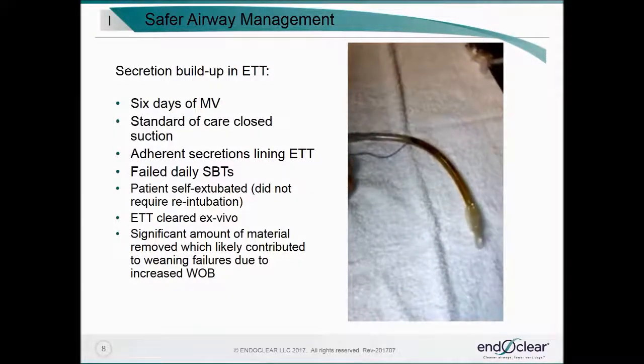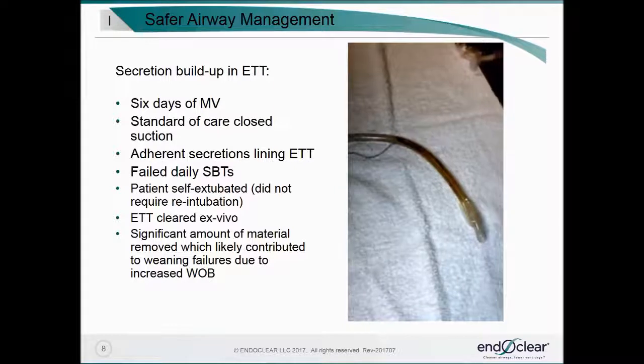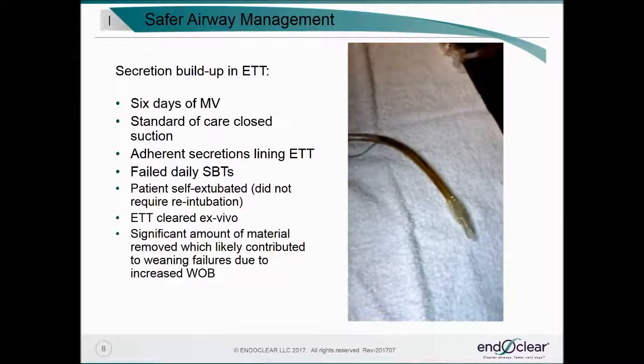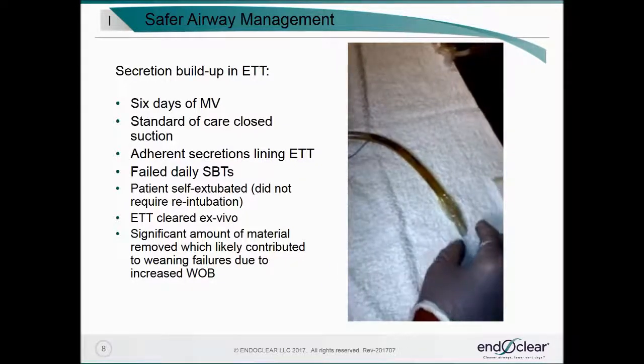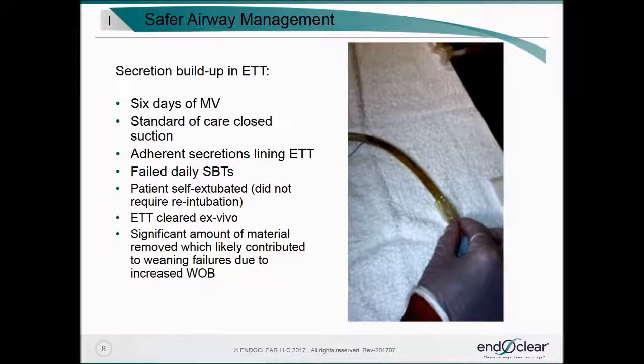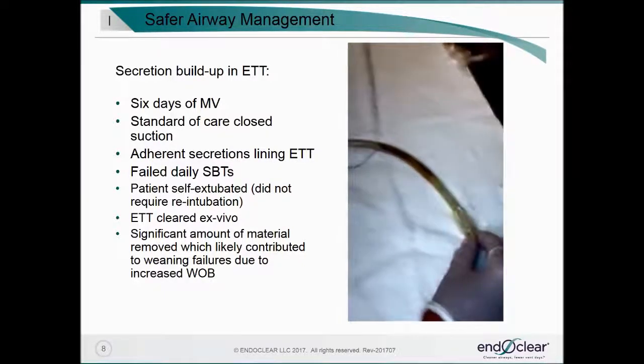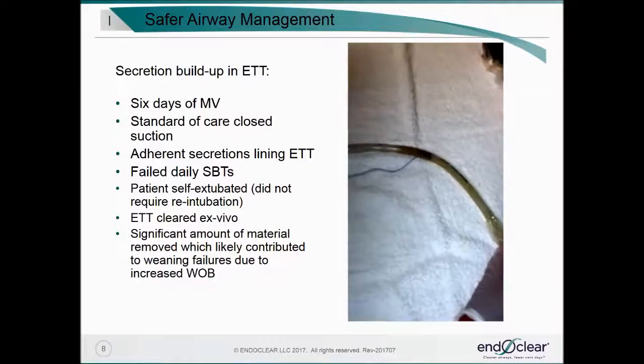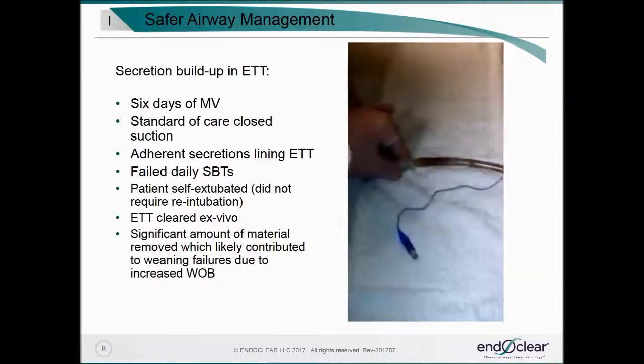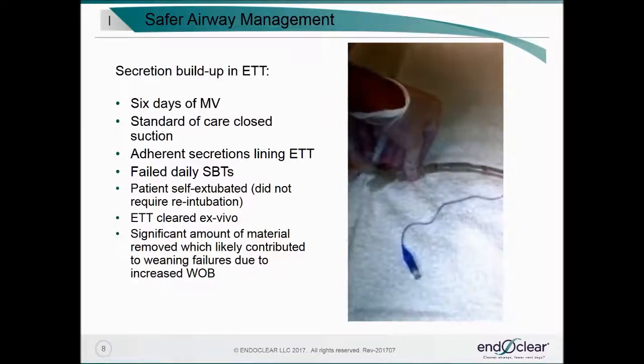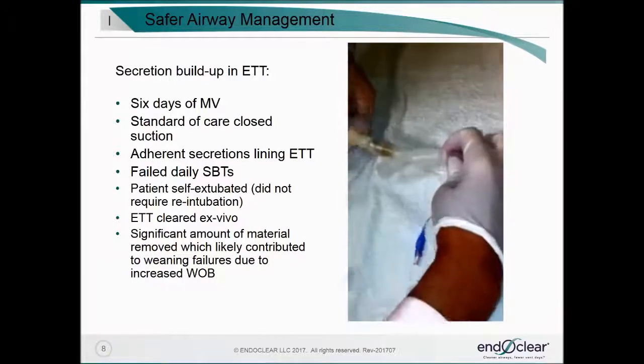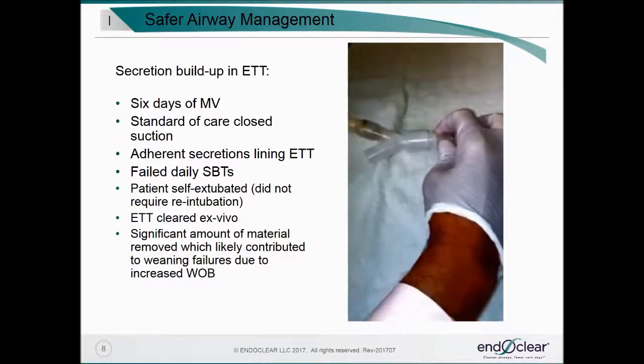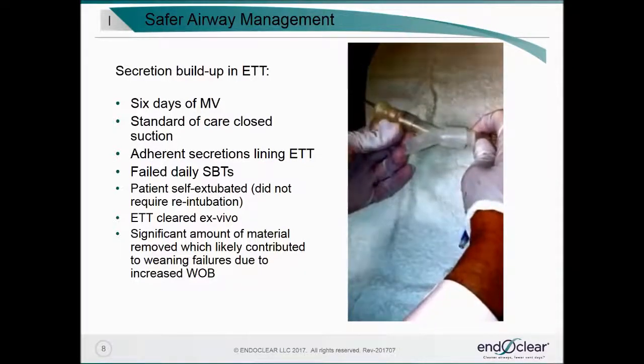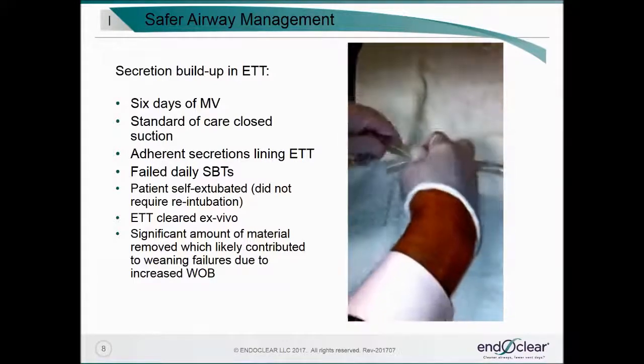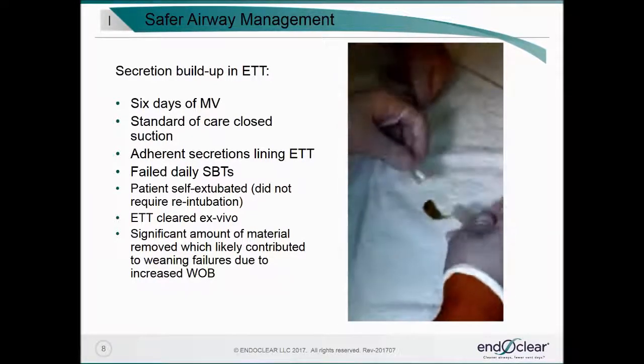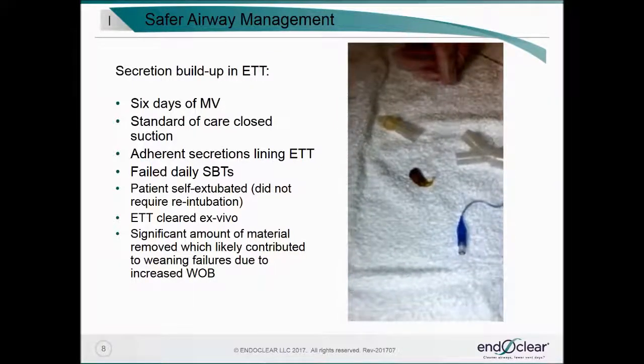This clinical example shows the consequences of retained endotracheal tube secretions. The patient whose tube is visualized here had undergone 6 days of mechanical ventilation, utilizing standard of care closed suctioning for maintenance of the airway. Adherent secretions developed and lined the endotracheal tube, and the patient failed spontaneous breathing trials on a daily basis. She then self-extubated and did not require reintubation. The ET tube that you see here was cleared with an ENDOCLEAR device, and as you will see, significant amounts of material were removed, which almost certainly contributed to her daily weaning failures, secondary to the increased work of breathing experienced.